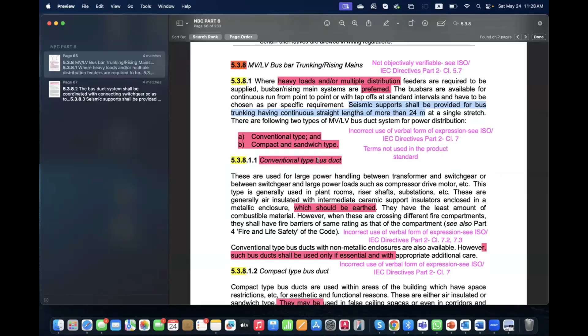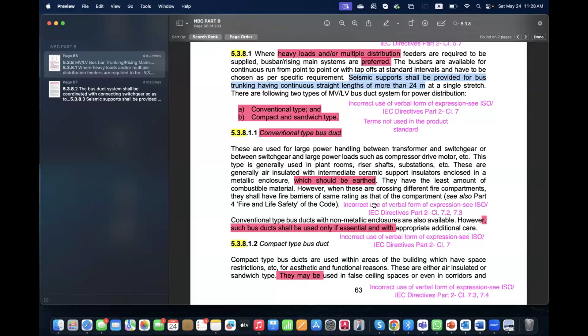These terms are not used in the product standard itself. How they have been used here, I don't know. Same thing with bus duct, we don't use this term. "Should be earthed": if you have a busbar trunking system with an exposed conductive part, the requirement from the product standard is that it shall be earthed, and the terminal shall be provided. Now you have a conflict between an installation standard and a product standard, and also the incorrect use of verbal forms of expression.